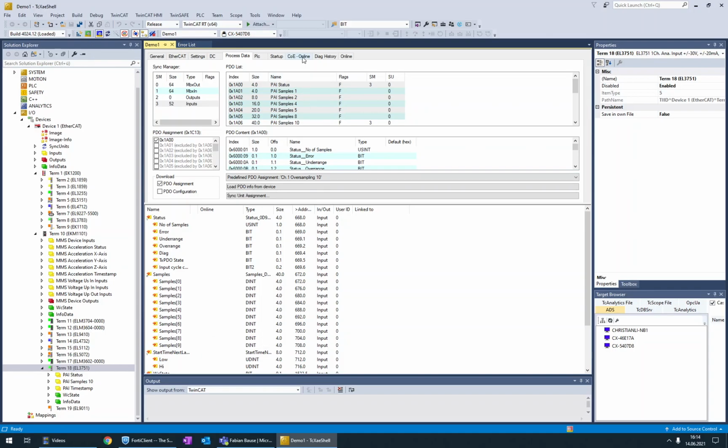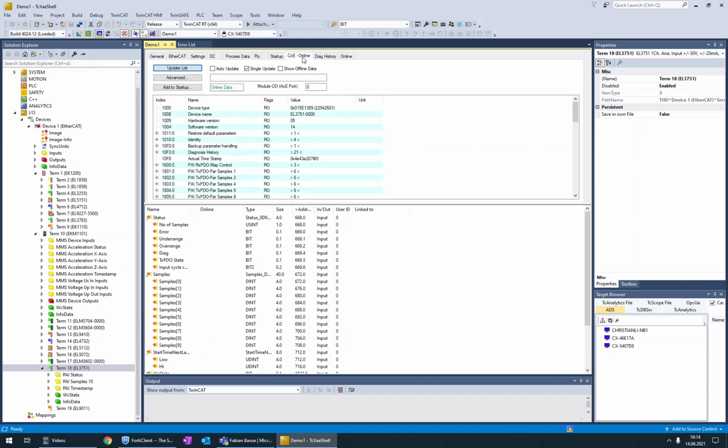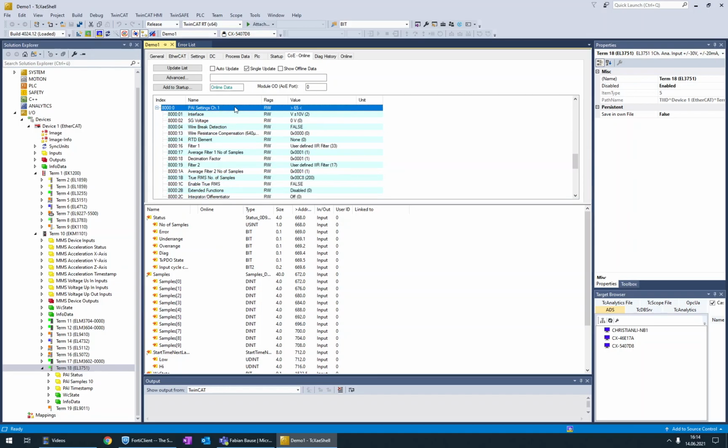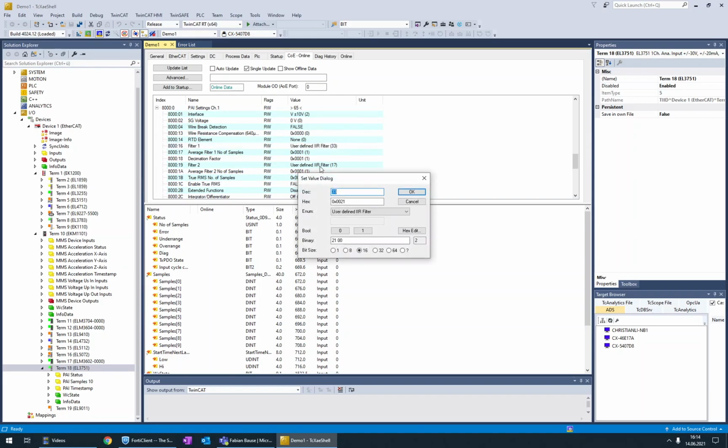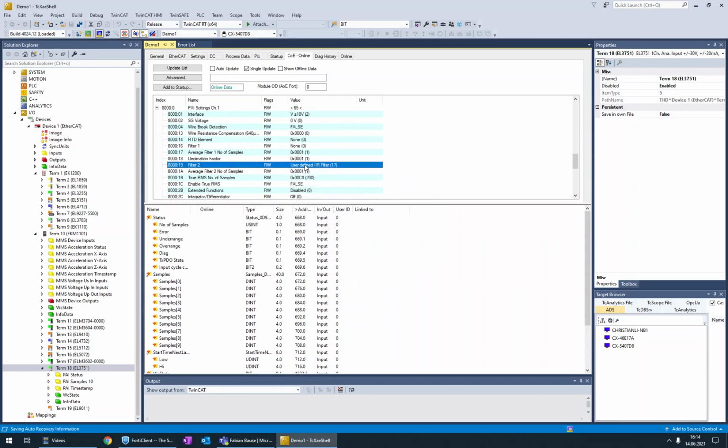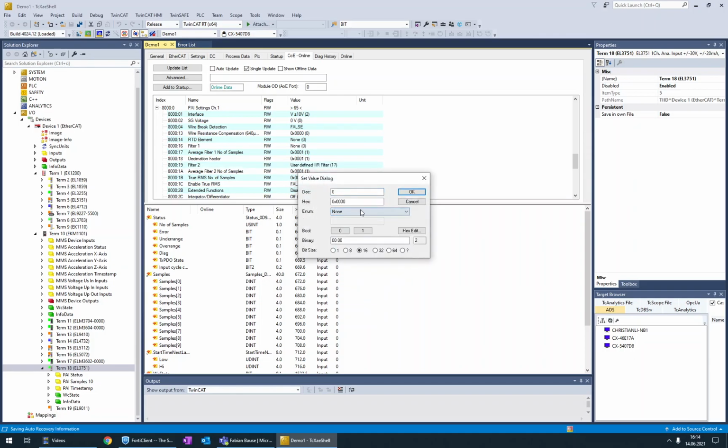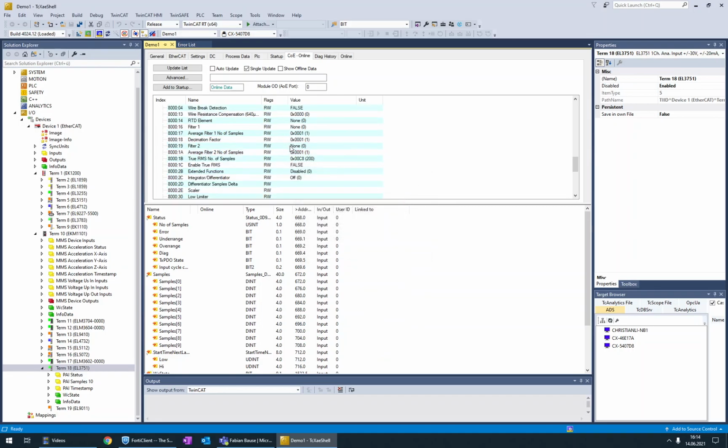We will also use the CoE configuration to jump to the number 8. You get directly to the samples of the specific channel. You configure it like you want. So in my case, there's a plus minus 10 volt configuration. I will first deactivate some filters. Filter bank 1 and 2 are now cleared. And so that's it. That is the first configuration.